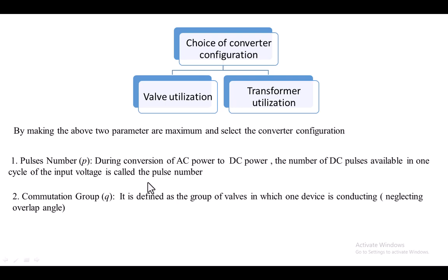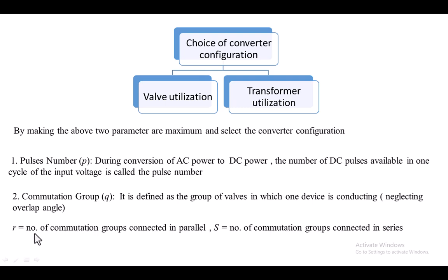We will first predefine the key variables. The pulse number: in an HVDC system, we are converting AC power into DC power, so the DC voltage consists of some number of pulses. How many pulses occur per one cycle of AC voltage is the pulse number. The second variable is the commutation group, which is a group of devices in which only one device is conducting, neglecting the overlap angle.